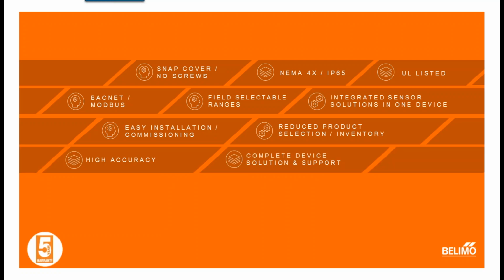So finally, a recap on some of the Belimo sensor features. They have a snap cover, no screws, NEMA 4X IP65 compliance, UL listed, BACnet and Modbus communicating, field selectable ranges, integrated sensor solutions into one single device, easy installation and commissioning, reduced product selection and inventory levels, high accuracy, and a complete device solution and support from Belimo. And last but not least, all covered by our 5-year warranty.